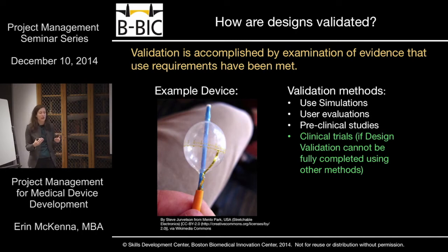Because a lot of devices come to market following the 510(k) equivalence method, they're typically pointing to some clinical experience through use simulations, user evaluation, and preclinical studies. But if you're developing something so new that you don't know if you can really make that leap with confidence, then you'll do a clinical trial as well. And there might be times, depending on what you're doing, even if the regulations may not say they want to see a clinical trial, that you may want to go get one.